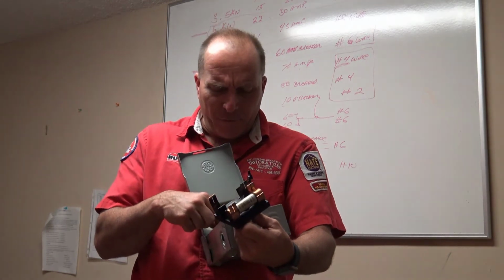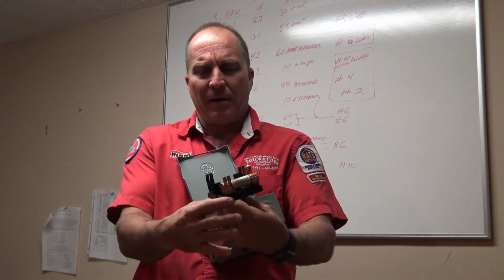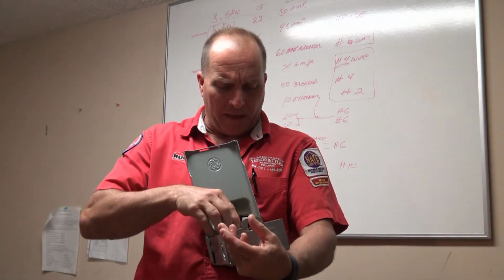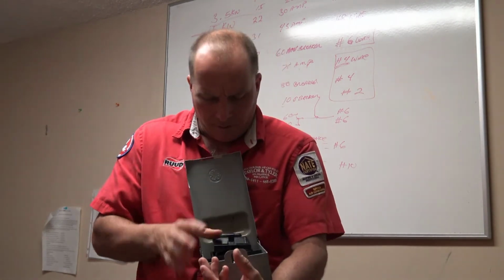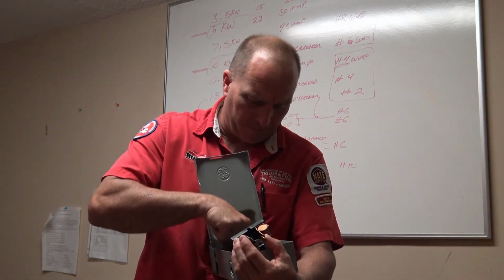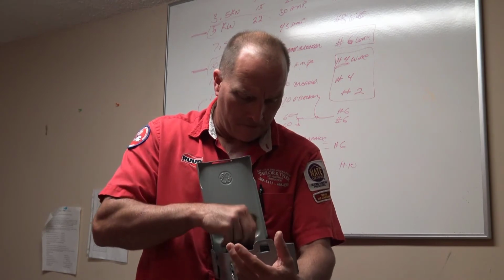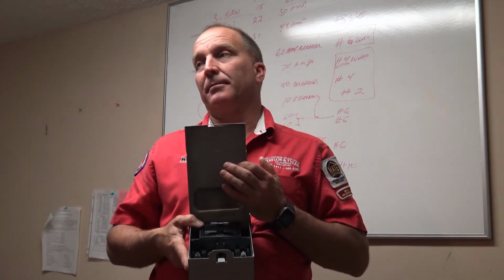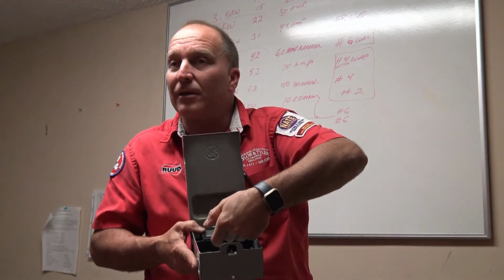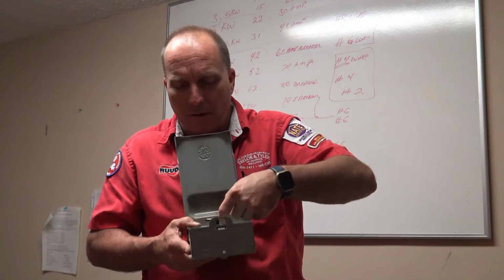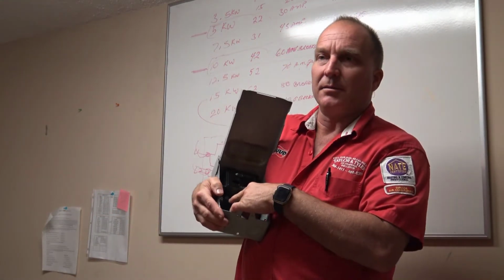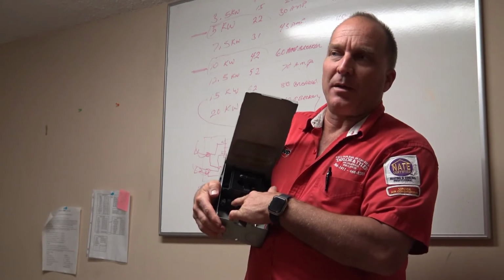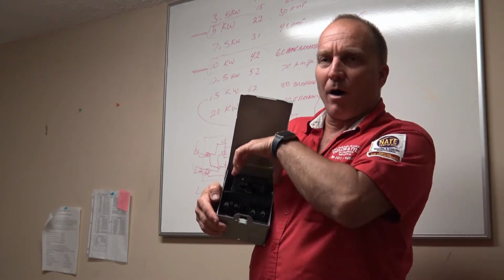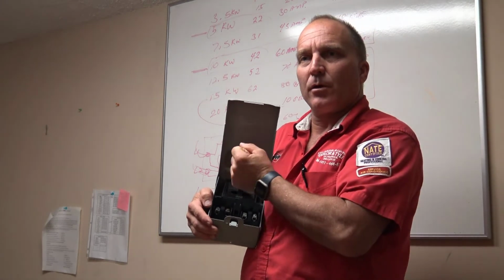So if you go to this specific unit and your fuse is still good inside of here, okay? And if you look at this, let me get it over there. It don't look bad, but the wires coming into it would be charred and burnt. And all of this could be caused by this wire not being tight. That's why part of your PMA is to do what? Take this panel off of here, stick your screwdriver in there and tighten each one of those wires.